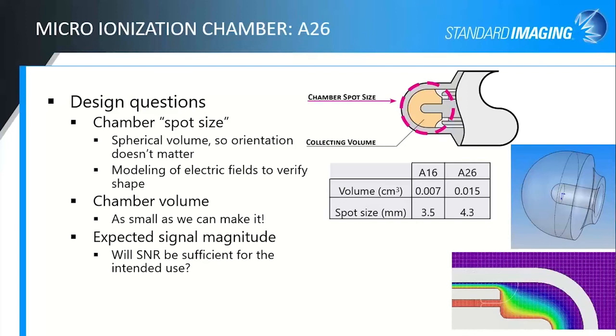If we look at our smallest chamber, the A16, the measurement volume is 0.007 cubic centimeters, whereas the A26 just about, or a little over, doubles that with 0.015. However, your spot size has gone up by less than a millimeter. 0.8 millimeters is all that we've added on the spot size for this one. So it's not a very big increase in spot size for a doubling of the signal, as well as better behavior. We made the chamber volume just as small as we can make it. I don't think you'll see a well-behaved chamber any smaller than this, just because of those electrical effects as well as manufacturing limitations. This is probably the smallest well-functioning chamber that you're ever going to see.